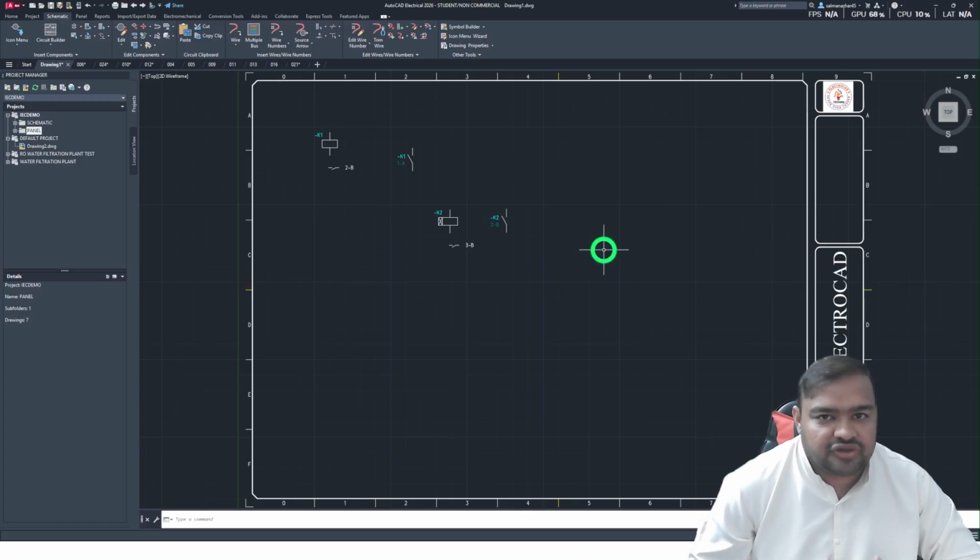So, what will we draw first? When we start drawing, we will not mix power and control. We will not mix logic on one sheet. Each logic block from the one-page diagram will map to one or two ladder rungs, with clearly named coils and contacts. This keeps the drawing readable and maintainable.